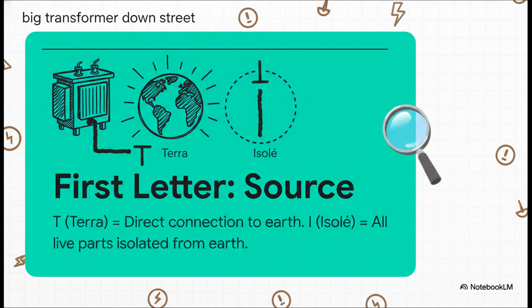The first letter is all about the power source itself. Think of that big transformer down the street. If it's a T, for Terra, that means the source is directly connected to the Earth. If it's an I, for isolate, it means it's isolated or not connected to Earth. Simple as that: T for tied to the ground, I for isolated.